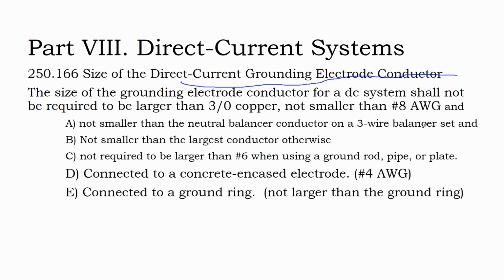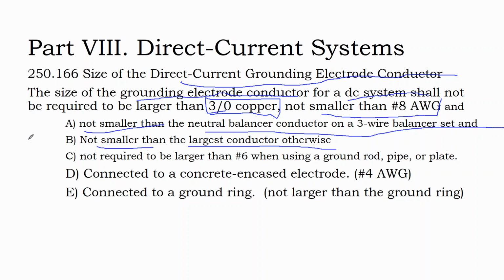It may be the same as your AC grounding electrode system. You may be bonding the DC to the AC, and you're going to do that down at your ground rod anyway. So can you bond your DC and AC grounding together? Yes, but you have to be aware that the DC grounding requirements may be a little bit different than the AC. The size of the grounding electrode conductor for a DC system shall not be required to be larger than 3/0, not smaller than number 8, not smaller than the neutral balancer on a 3-wire balancer set, not smaller than the largest conductor otherwise, and not required to be larger than number 6 when using a ground rod. Often we'll use a ground rod so that our grounding electrode conductor up to the rooftop is not required to be larger than number 6.